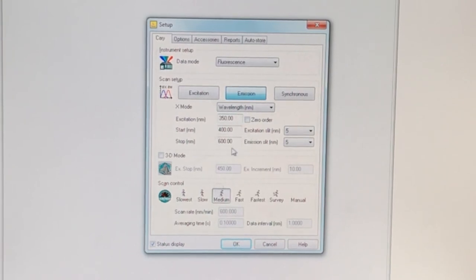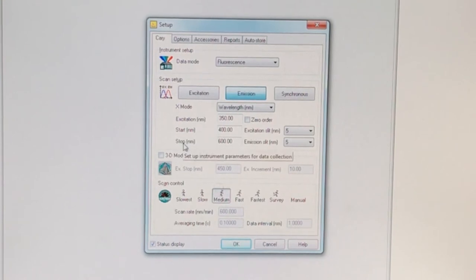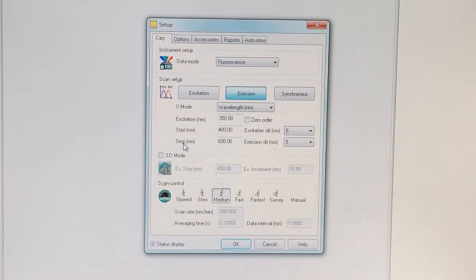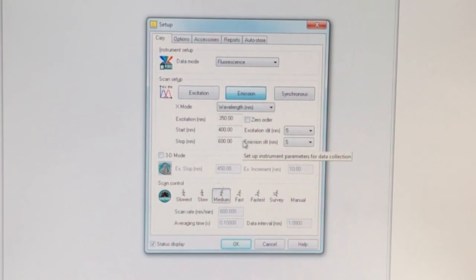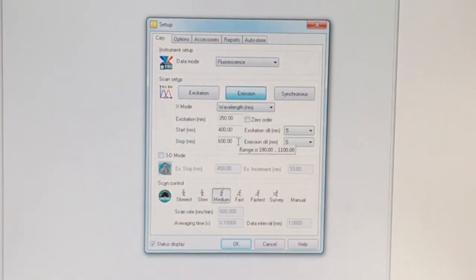The stop wavelength. This is something where if you have a well-defined sample, you know where the spectrum should be. You can set this up. If you don't know where the spectrum will be, you can set this since the range is out to 1100 nanometers.